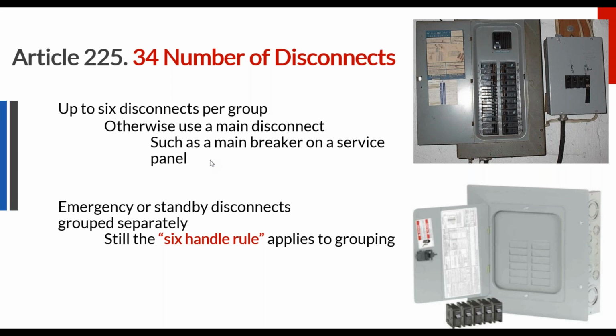Or you might have an external disconnect switch, like a knife switch disconnect. And so if you're already using the knife switch disconnect, then you may say, well, I don't need that main breaker up top because I already have the main disconnect switch right next to the equipment. So adding yet another disconnect switch would be redundant. Or you could get into that the inspector wants a knife switch on the outside of the wall, but you'd still have your main breaker on top of your main service panel inside the wall, and eliminate the confusion over the additional exterior disconnect, or what this rule is. But essentially, if you have 6 switches and you need to power down something that you're immediately around, no more than throwing 6 switches.